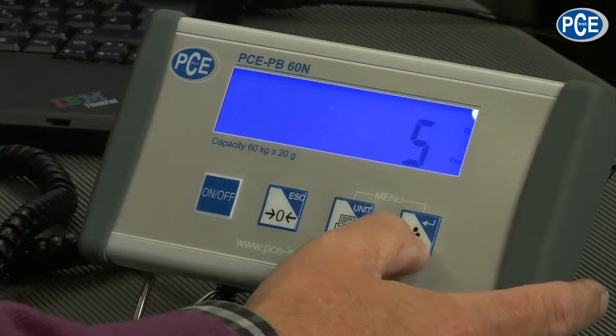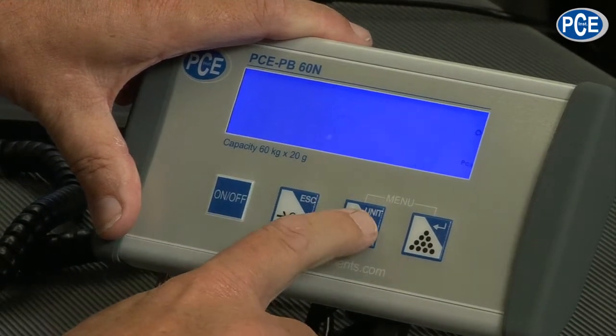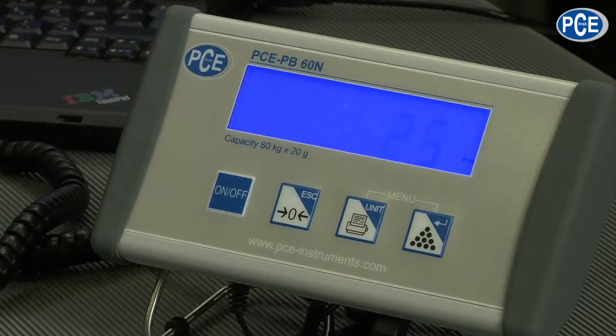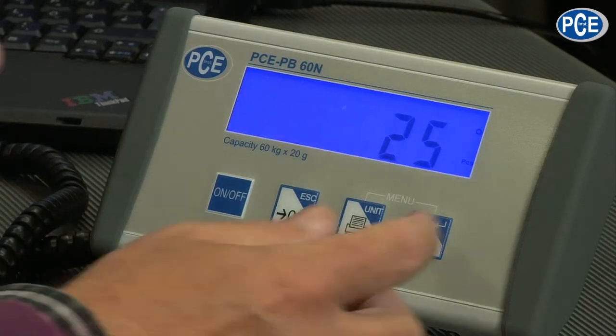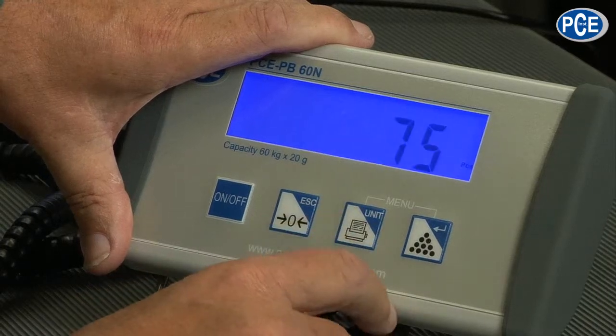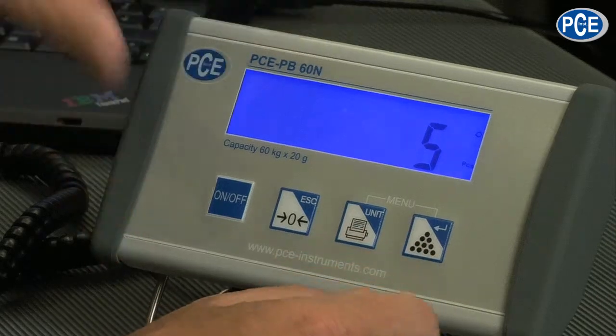There are other functions. Imagine I have here cans - thousands of them and I have to count them. I cannot be bothered to count them manually, so I tell the scale: I would like to count now. I say that there are five pieces, or ten, twenty, thirty. When I have screws or other small items and have lots of them, I take more for a more exact reference weighing - fifty, seventy-five, a hundred. Now I set it back to five and say OK. That is five cans, and the scale remembers it. Now I put one more on: six cans, one more, seven, eight, nine, ten - it can count just like me, but it does not miscount. So I also have a counting scale.